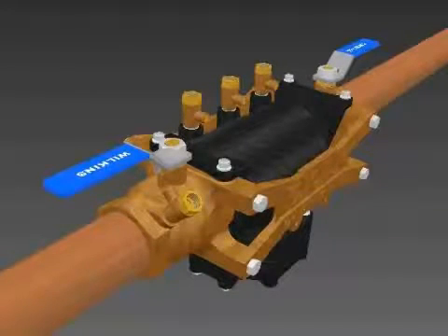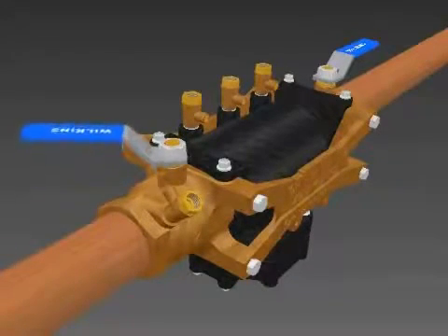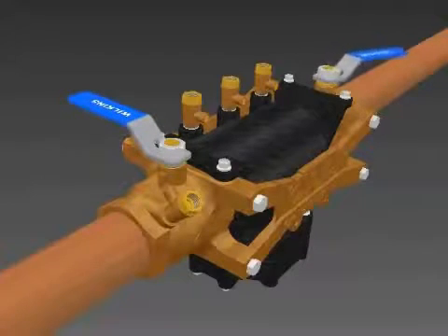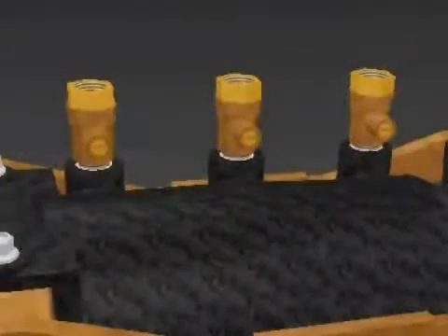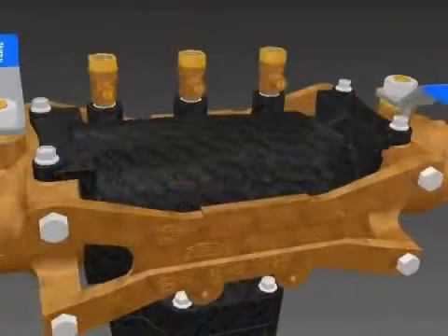To begin the repair process for a Model 375 in 1 1/4 to 2 inch sizes, first close the inlet and outlet shut-off valves. Open the number 2, number 3, and number 4 test cocks to release the pressure from the valve.